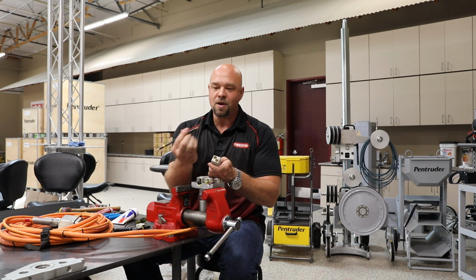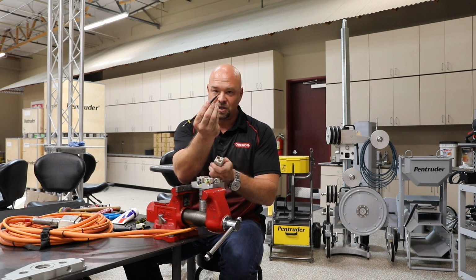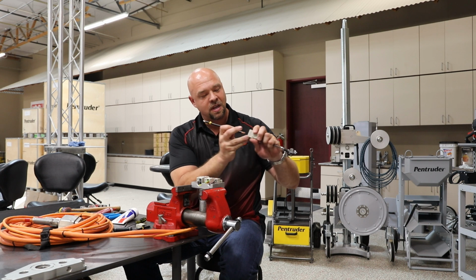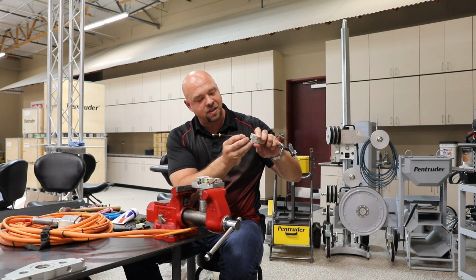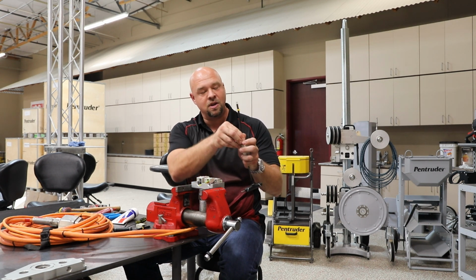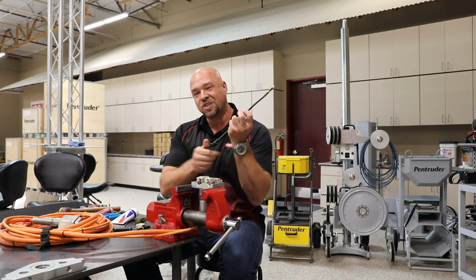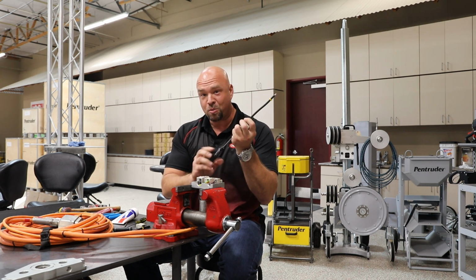When you insert the wire, once you've got it nice and clean and tight, and you've just removed your insulation and shielding, insert it directly into the back of the connector and push it firmly. Hold it there while you tighten the front of the connector down using that 4 millimeter wrench.